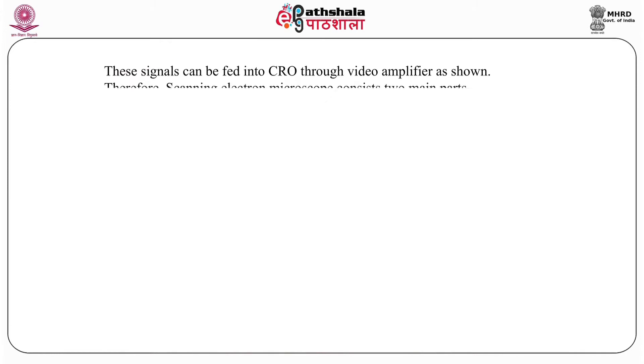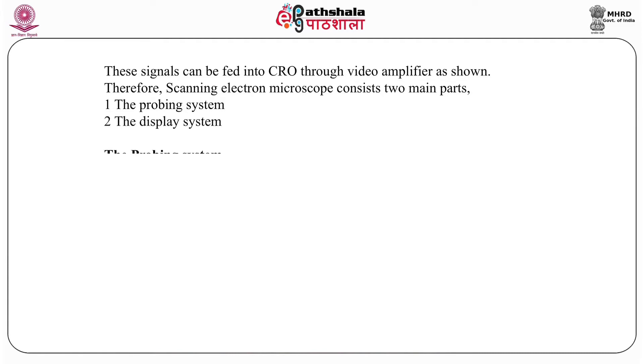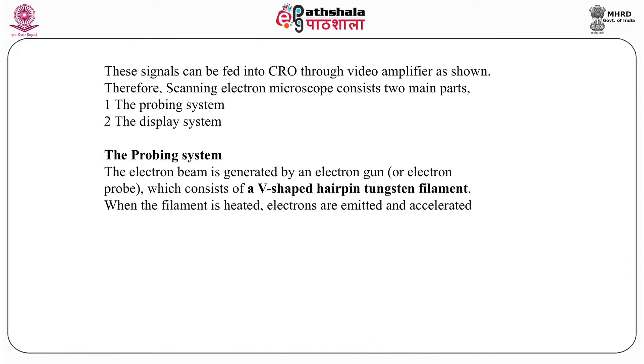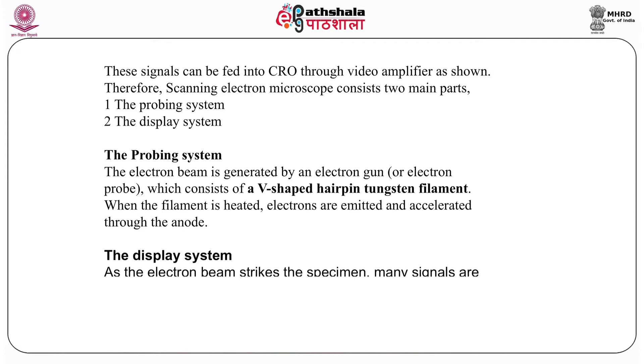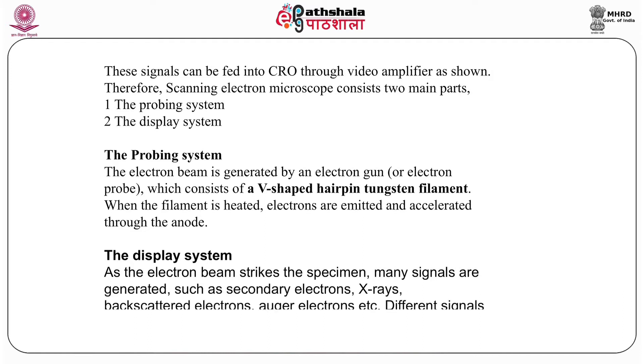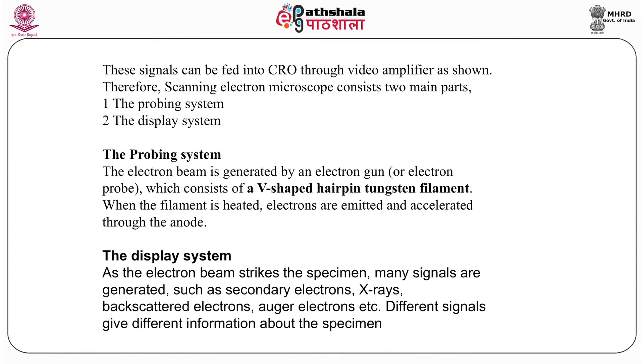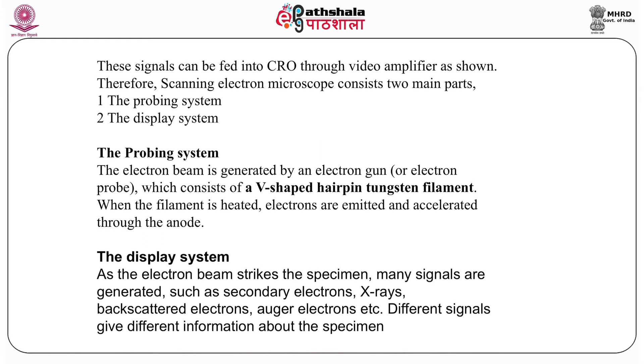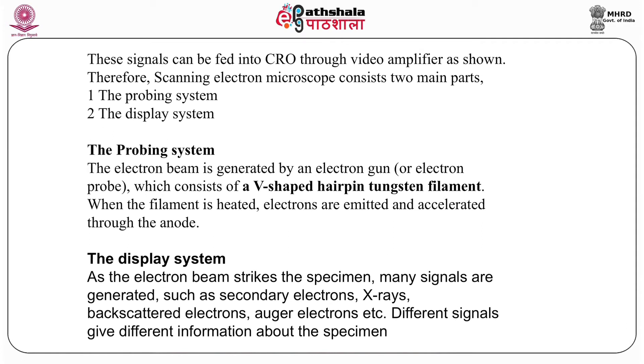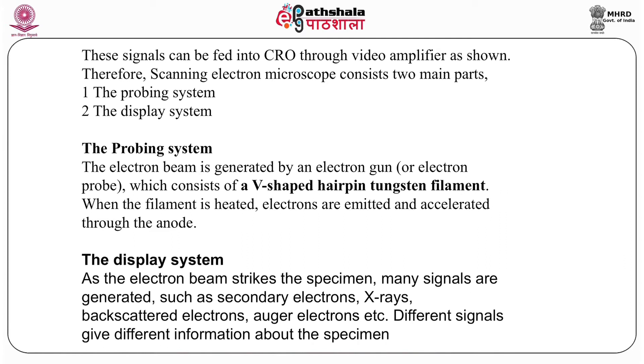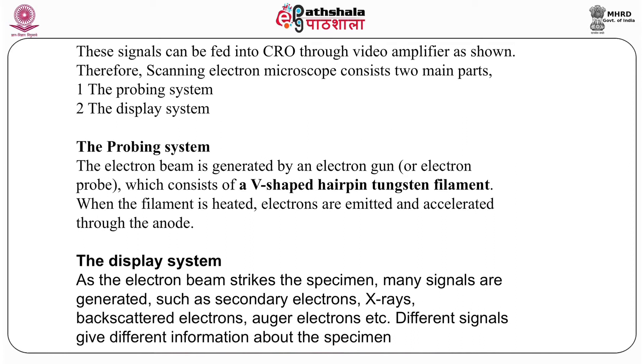In SEM, the signals can be fed into a CRO and the image is amplified. There are two basic components: a probing system and a display system. In the probing system, the electron beam is generated by an electron gun consisting of a V-shaped hairpin tungsten filament; the filament is heated so electrons are emitted and accelerated through the anode. In the display system, after electrons hit the specimen, many signals are generated: secondary electrons, X-rays, and backscattered electrons.